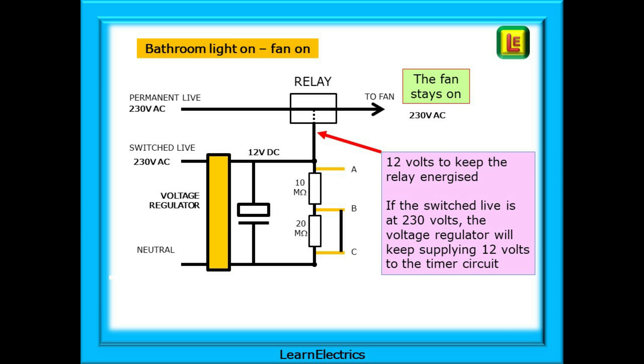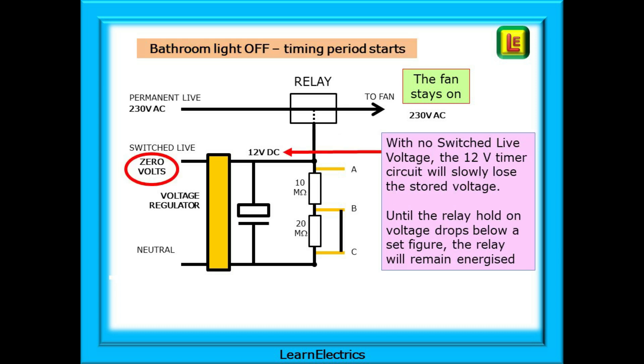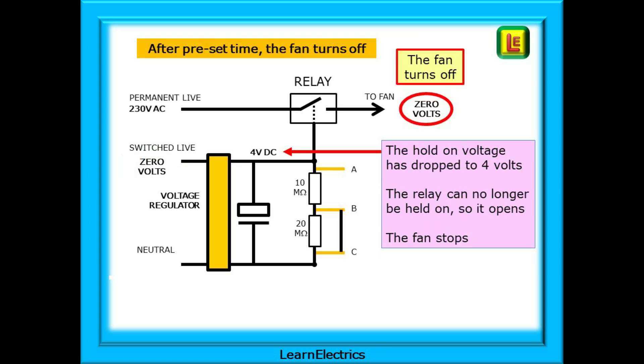Whilst the light is on there will always be 230 volts on the switch live, which means there will always be 12 volts to keep the relay in the on position. If the light is turned off, the switch live drops to 0 volts, but the 12 volts does not drop to 0 straight away. The capacitor has stored some electrical charge and this slowly seeps away depending on which resistor the links or switch have been set to. As the electrical charge drains out through the resistor, the voltage will slowly fall from 12 volts to 11 volts to 10 volts and so on. The relay will hold itself in the on position if the voltage is above say 4 volts, and the fan will stay on. When the voltage drops below 4 volts, this is not enough to hold the relay in the on position, so the relay drops out and the contacts open. When the contacts open, the permanent live is interrupted — no voltage can get to the fan and the fan stops.